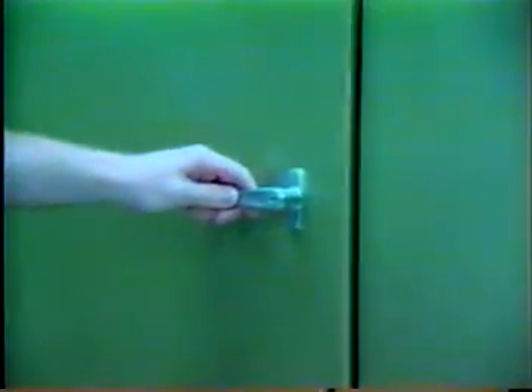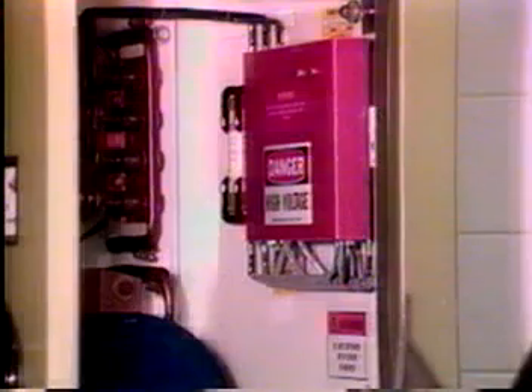For example, in the latest induction installations, current handling bus bars and components are covered by protective enclosures. To provide additional protection, there are several types of safety interlocks designed to turn off power if power supply access panels or doors are opened. But for these and other safety systems to be truly effective, all workers must respect the protection these systems provide and not override or defeat their functions. The following are some basic rules for electrical safety in the melt shop.